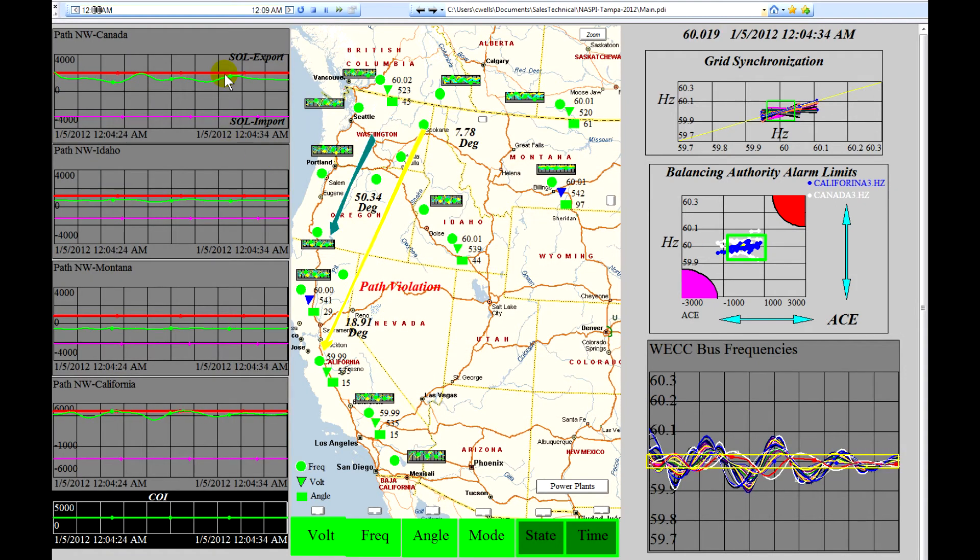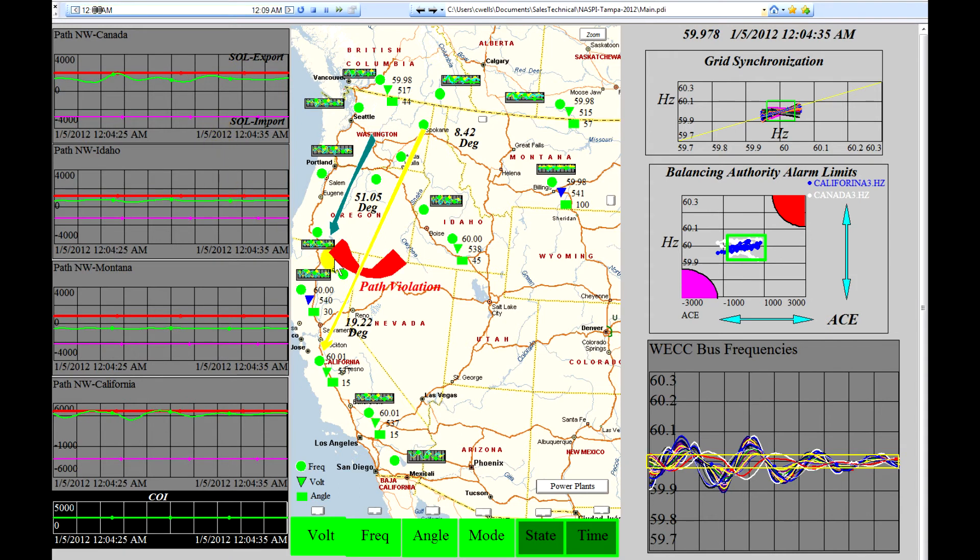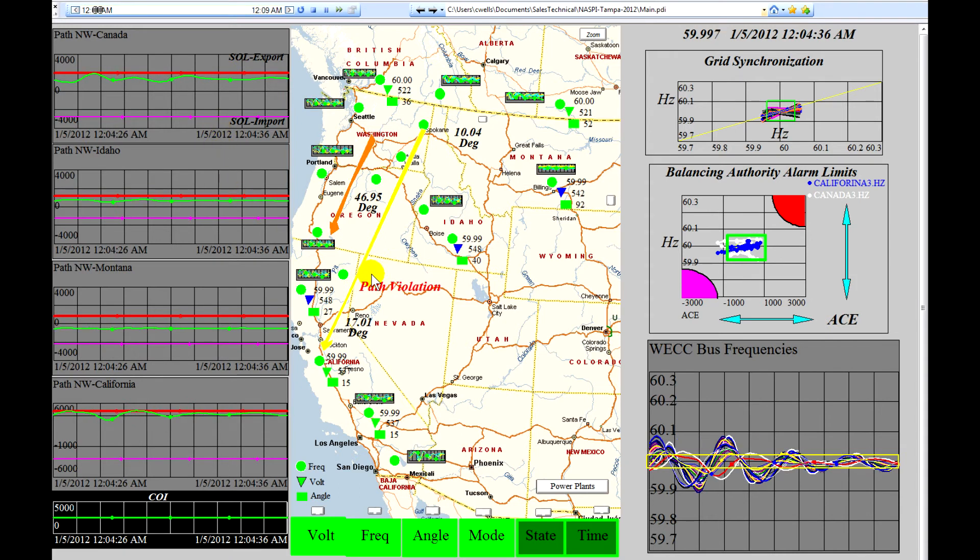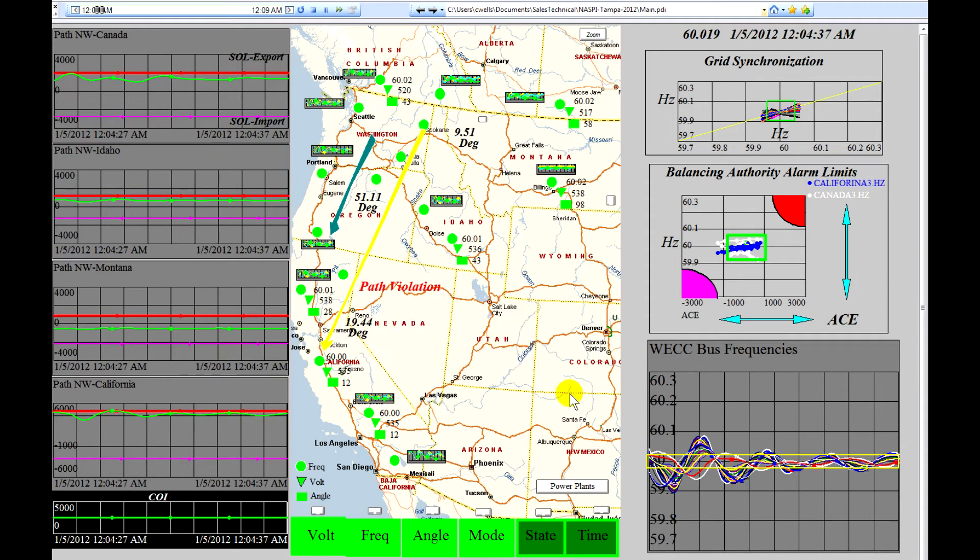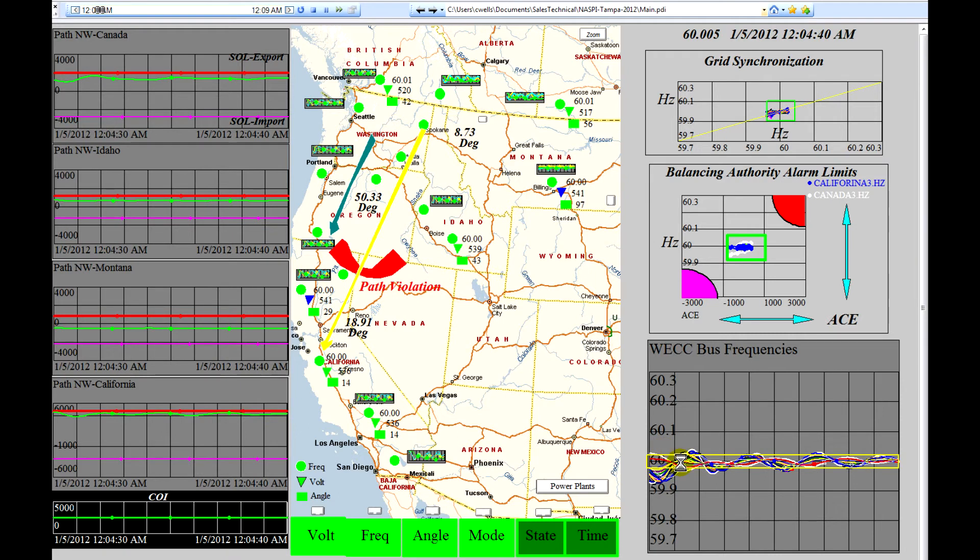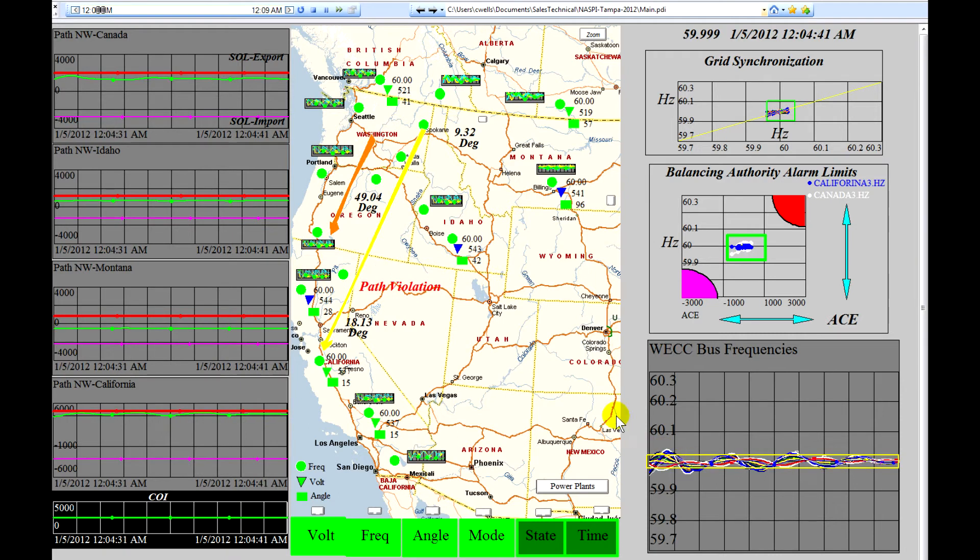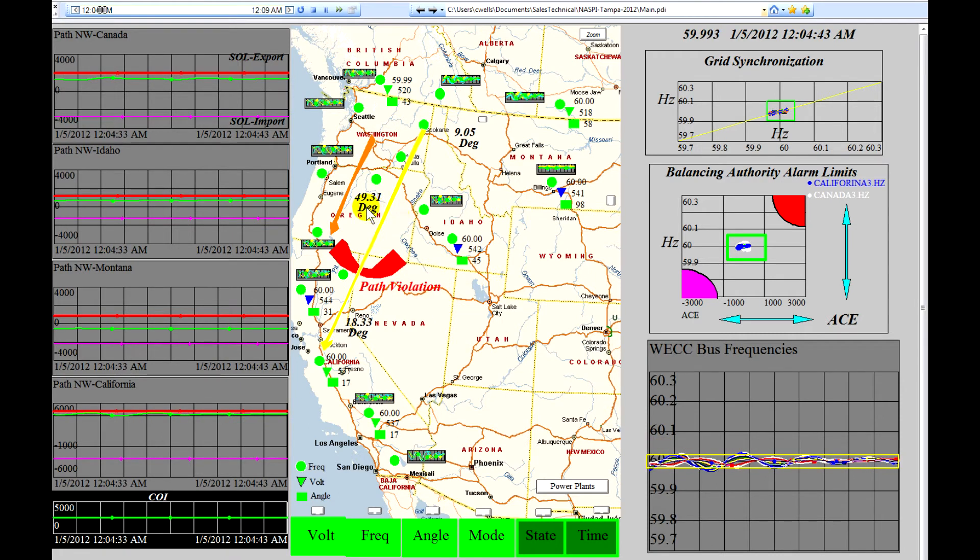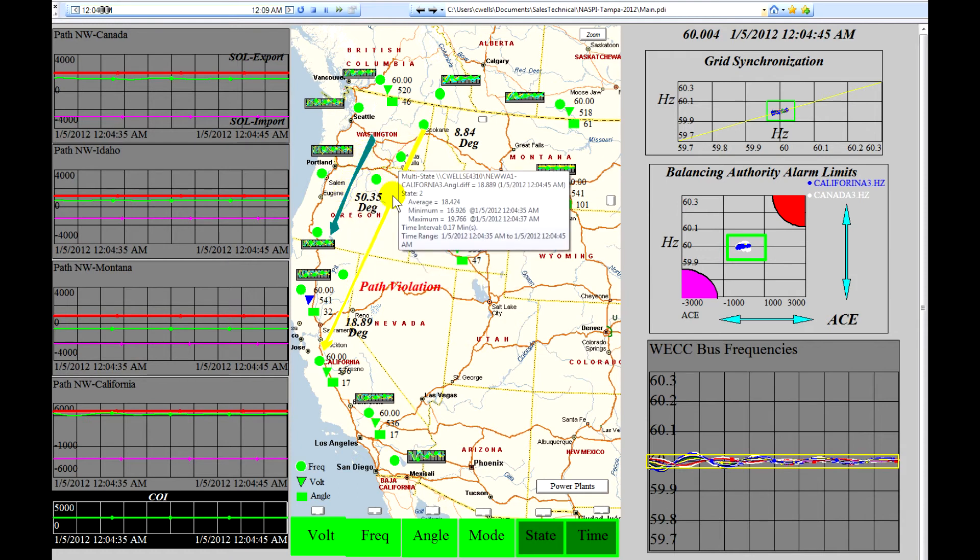These are showing the path. We have a path violation occurring. We've had a significant disturbance shown by the oscillation here. And we have fairly large phase angles between Washington and Oregon and Washington and California.